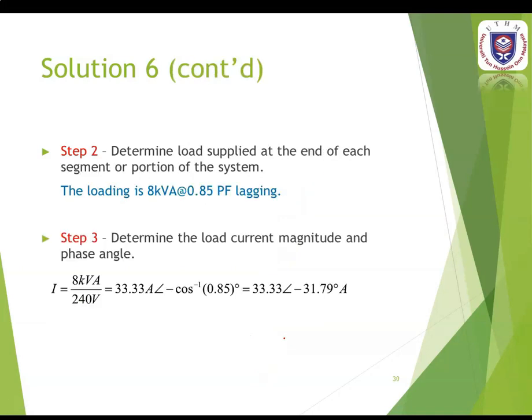The second step is to determine the load supply at the end of each segment or portion of the system. In this case the load is 8 kVA, which is the apparent power with 0.85 power factor lagging. The third step is to identify the load current magnitude and the phase angle. For single phase, current equals apparent power divided by voltage. You get the current value 33.33 at angle negative 31.79 degrees ampere.